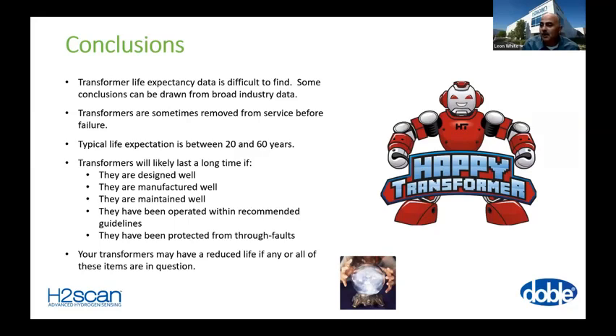And so the concern, of course, is whether the transformer you're putting in to replace it is going to last as long as the old transformer would have lasted if you had left it in service. I like to say that your transformers will likely last a long time if they're designed well, manufactured well, maintained well, operated within recommended guidelines, again, minimizing through faults, and so forth. And I know Tony has some additional things to say here. You're very prescient.